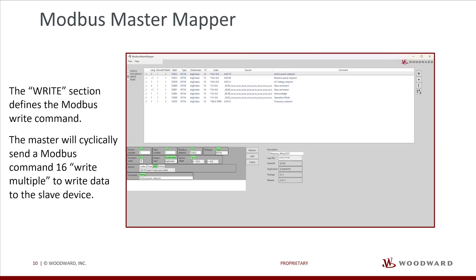The write section defines the Modbus write command. The master will cyclically send Modbus command 16 — write multiple — to write data to the slave device. The list is always automatically sorted by: 1) device, 2) rate, and 3) Modbus address.